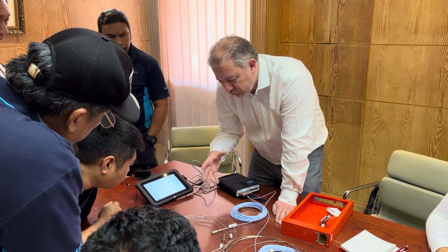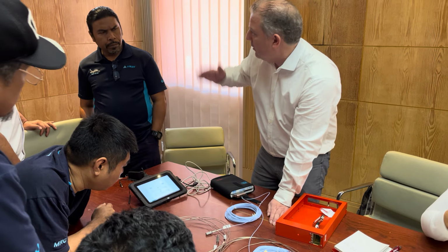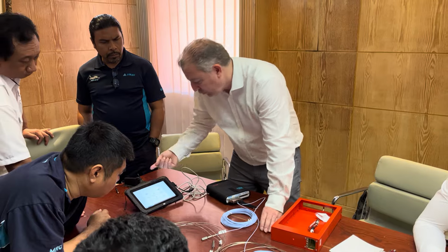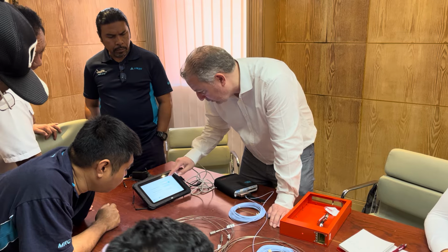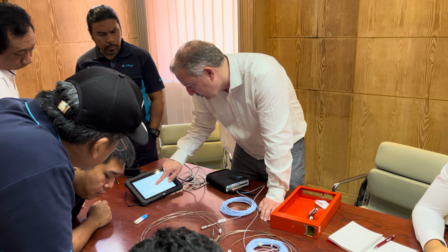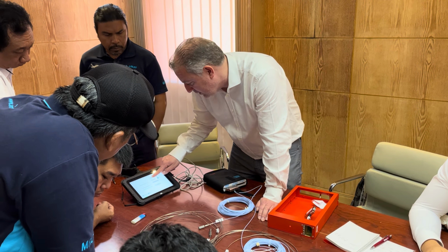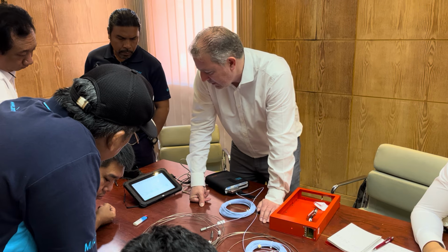Okay, so it sees the open here. That's the very basic condition. That would give you this diagnostics for all the loops. And then if you want to troubleshoot, then I can come back to expert mode. I launch new test. Instead of selecting all, I select the loop I want to check. I go to static test again.